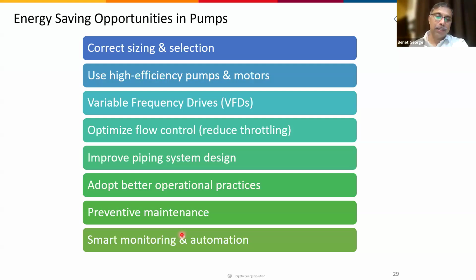Then adopt best operational practices. In some cases, for example, you have a firefighting system: what is the pressure to be maintained? Or if you have a hydropneumatic system which maintains the same pressure, especially something like water pumps for domestic water requirement. Then do preventive maintenance, lubrication, and checking of the pump. So all this will help. Then smart monitoring and automation checking.